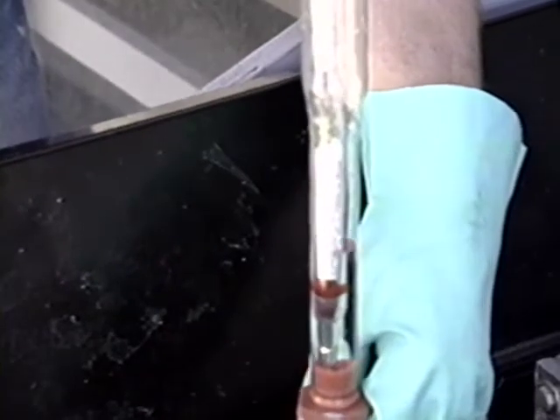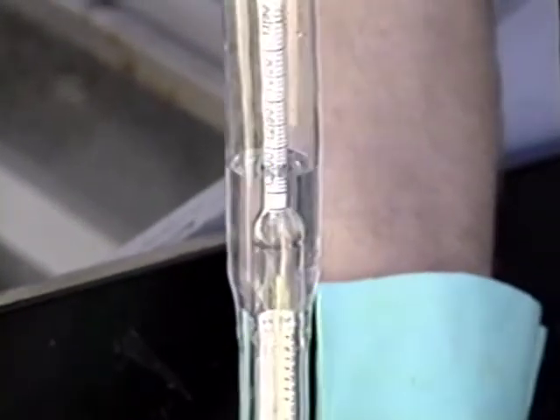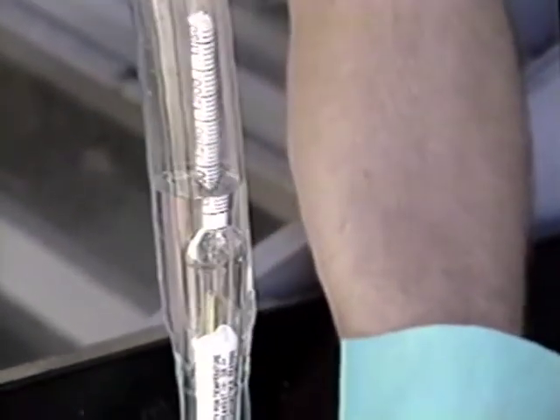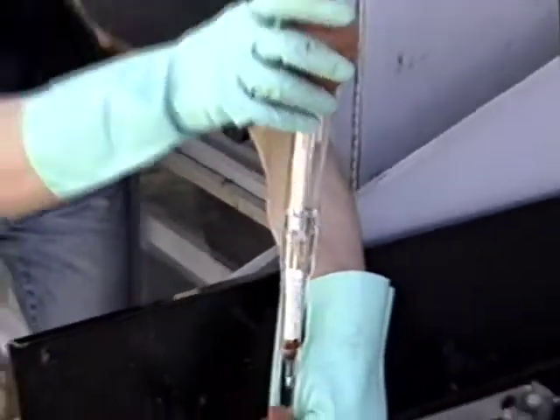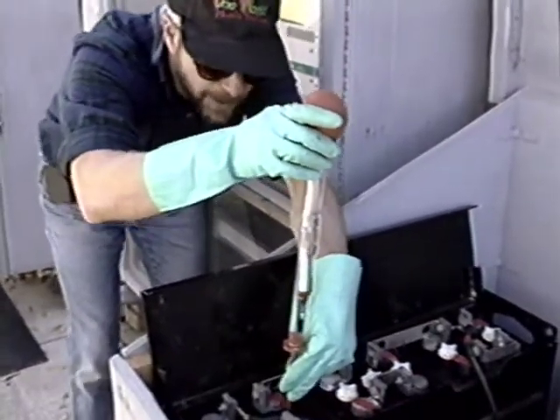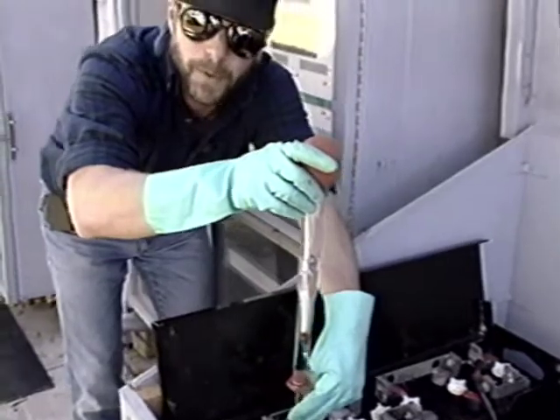Cells in a battery bank are kind of like horses in a team. If you get one horse that's dragging or one horse that's pulling too fast, doing a runaway action, it's going to affect the performance of the whole team. So you really need to check the hydrometer reading for every single cell to make sure that the batteries are working well together.